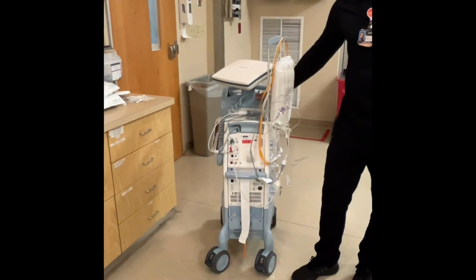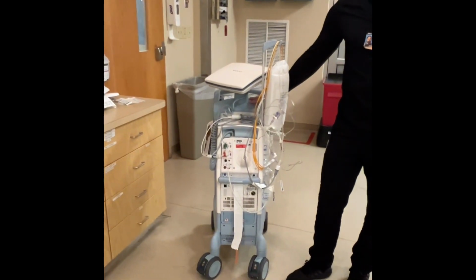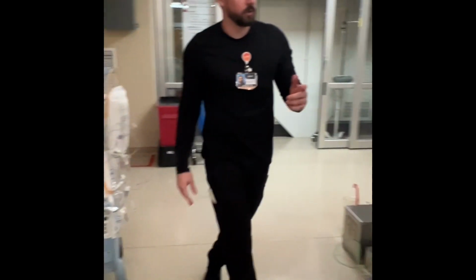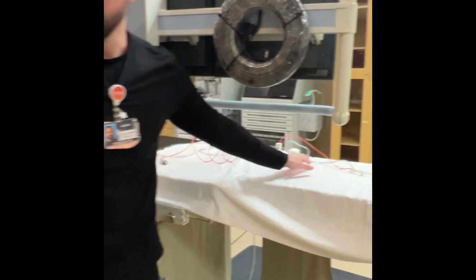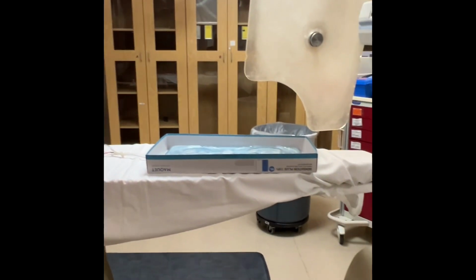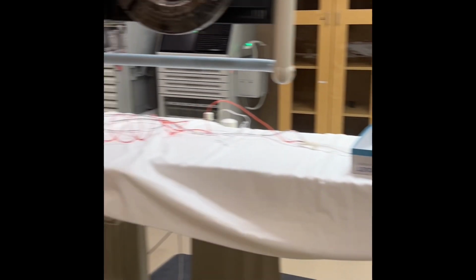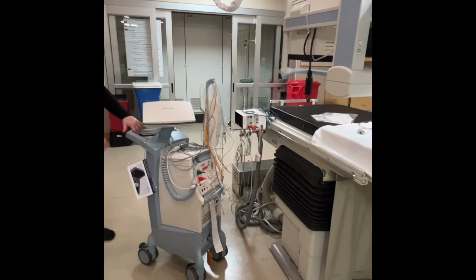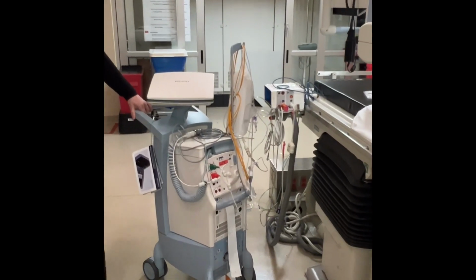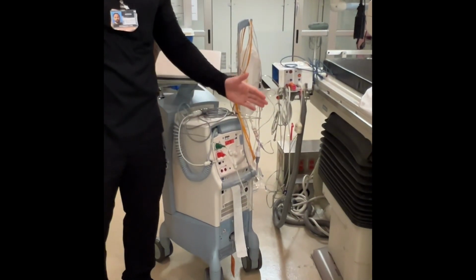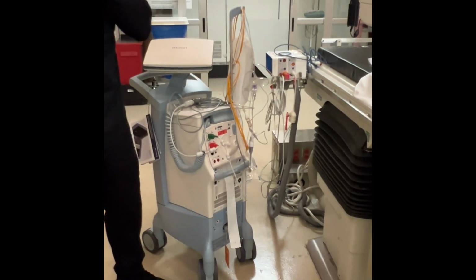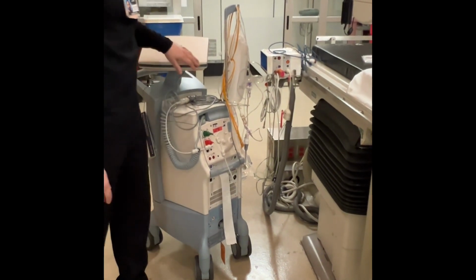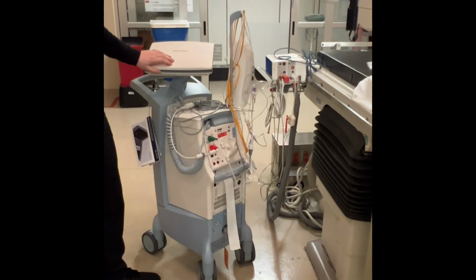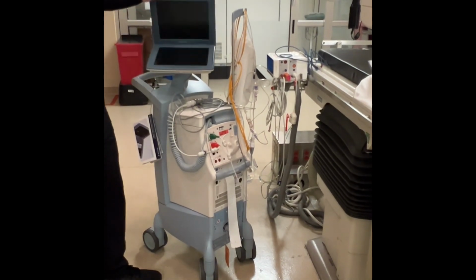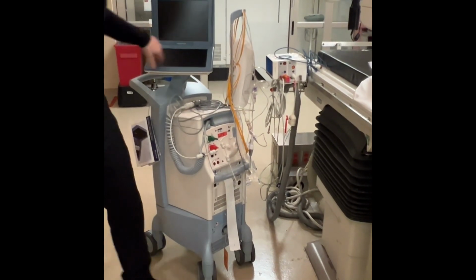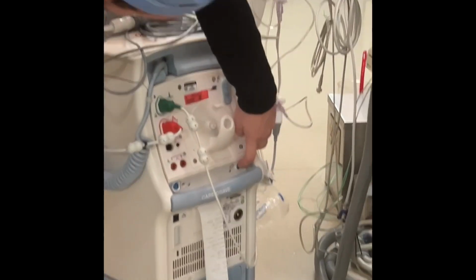When they call for it, generally the cath lab tech will go and get the actual balloon itself while we're setting up the machine. So you're going to unplug it, grab it from the wall, wheel it up to the table, and you want to make sure this side of the machine is facing the table, because that's where all your connections are going to be made. As soon as you get it over here, the first thing you want to do is turn it on. You're going to open the console here, and the power button is this little green guy right there.